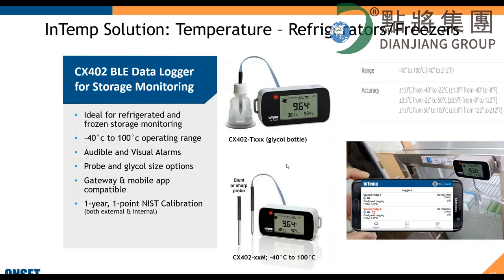This device comes with an external channel, the probe, and then you have a second temperature channel. So it's a two-channel data logger. You have the internal one and the external one, so you can at the same time measure the ambient temperature around your equipment. As I said, these are mainly used for fridges and freezers, and they have an operating range from minus 40 to 100 degrees. You can have local alarming by audio or visual alarms in the display, and within the display you can also see if you have a low battery notification.